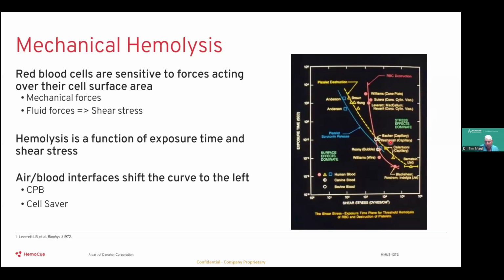And one of the interesting things that happens is that an air-blood interface, which can happen in things like cardiopulmonary bypass or cell salvage systems, will actually shift this curve to the left, meaning that less shear stress for less time exposure can create the same level of hemolysis that a high shear stress for a short time exposure would engender.